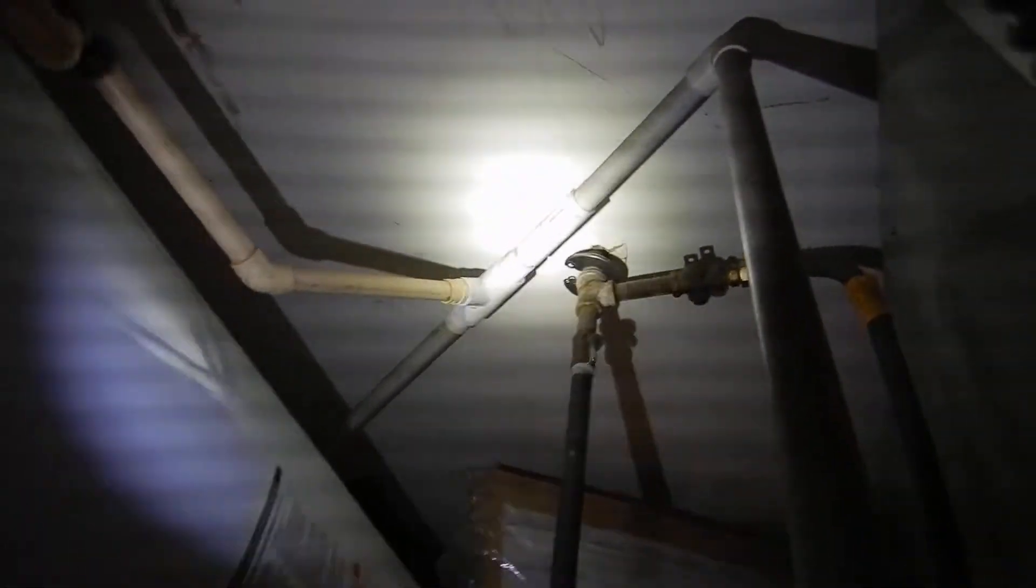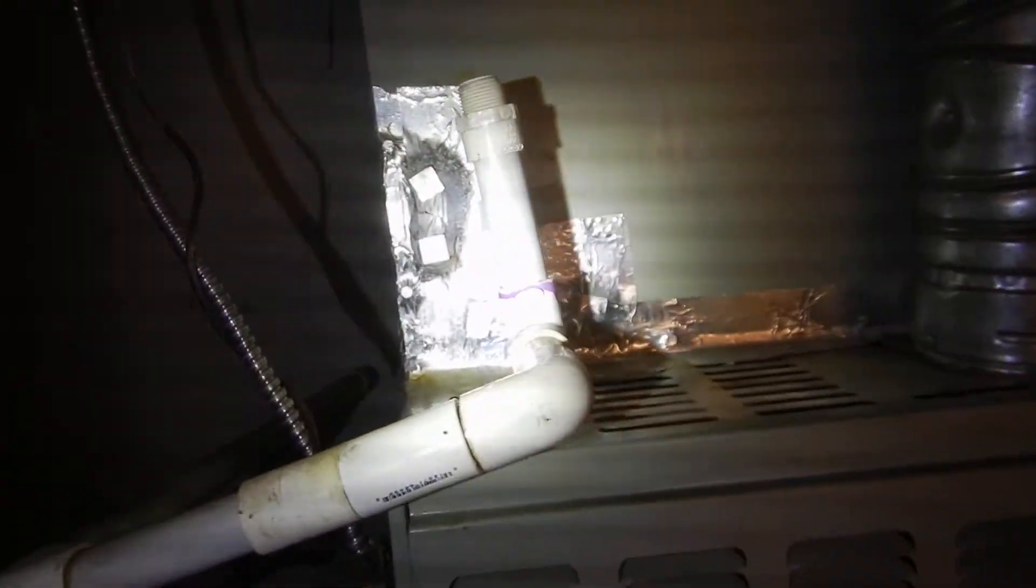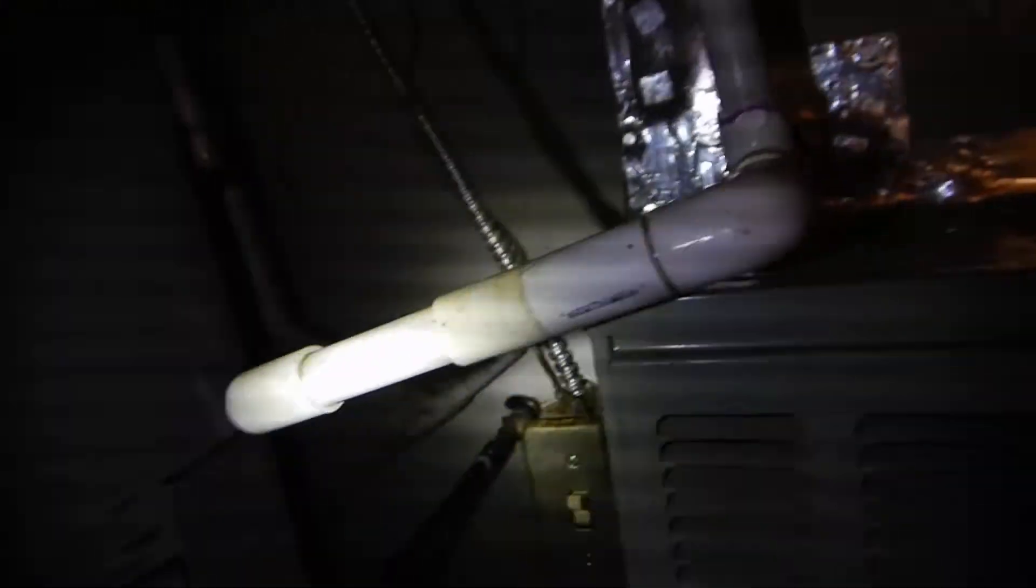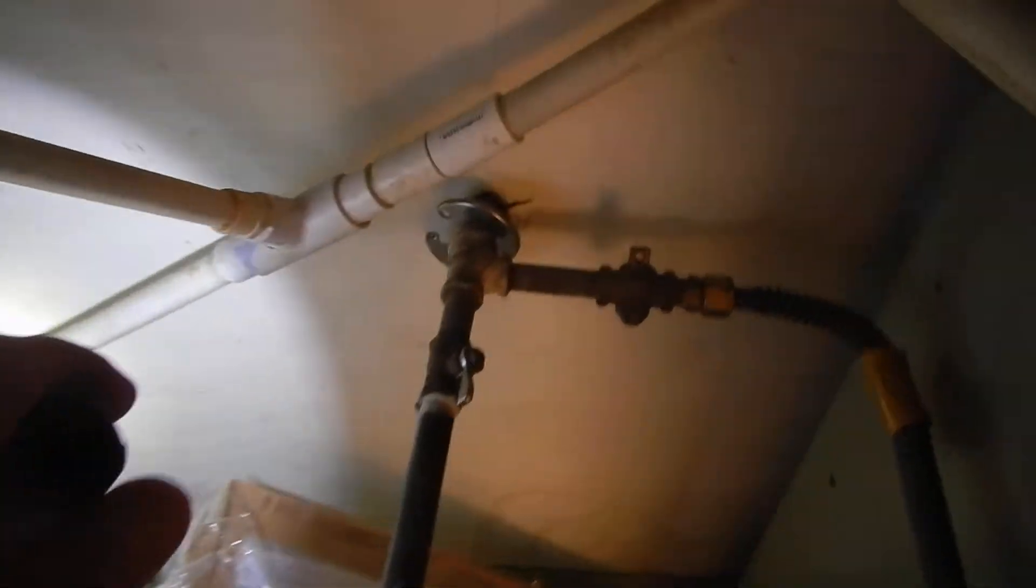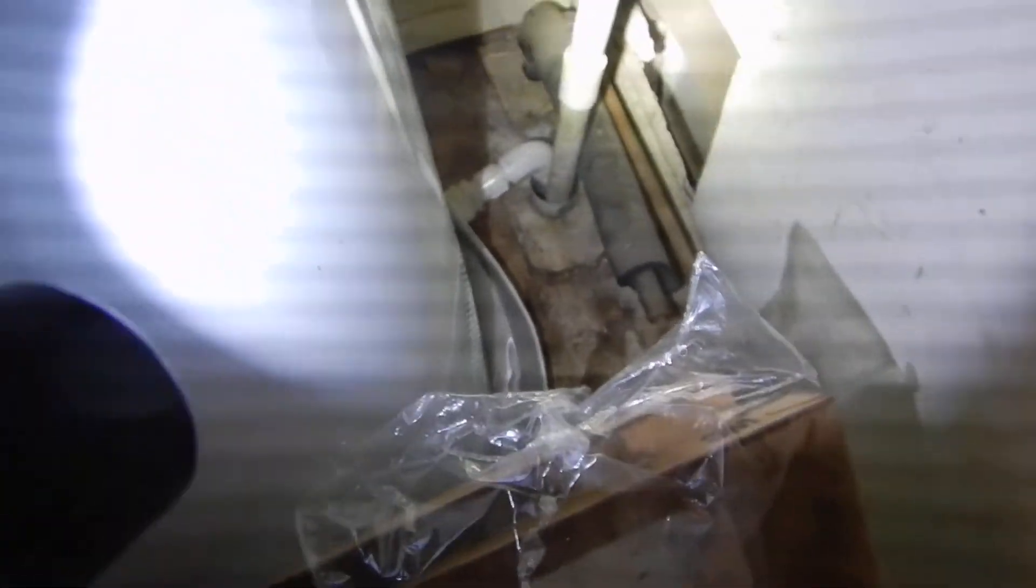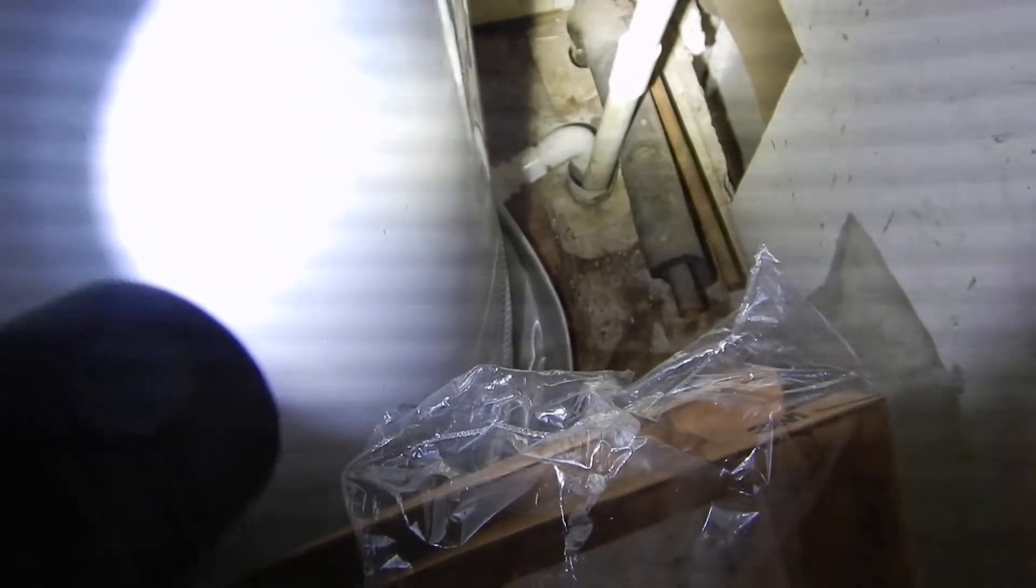And it comes down, and where does it go? It goes to the, we already talked about this, the HVAC evaporator coil drain line. They are commingled. They're not supposed to be commingled. This goes into the drain, okay. This is supposed to go to the exterior somewhere, which obviously it doesn't. It goes to that drain right down there. There's your safety pan drain.